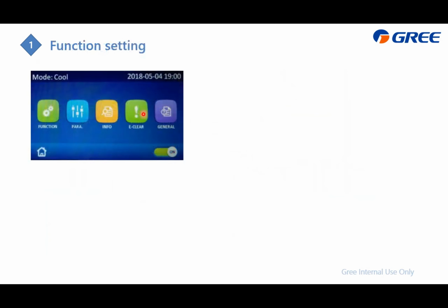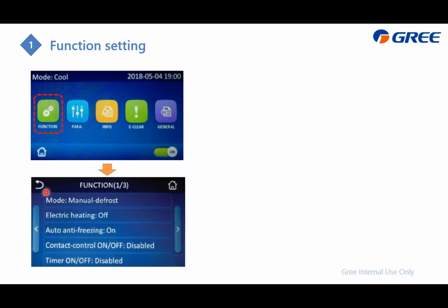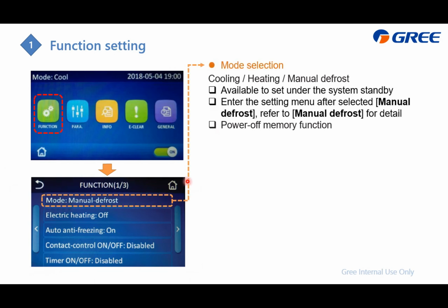Function setting. On the menu page, when you press here, it will go to the function page, which is this one. Here you just need to turn different functions on or off. The first one is the mode selection. For the chiller, there are these three: cooling, heating, and manual defrost mode. You can choose manually.